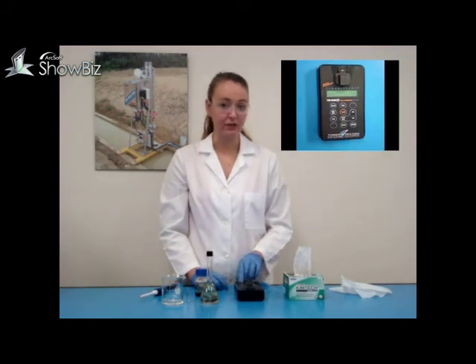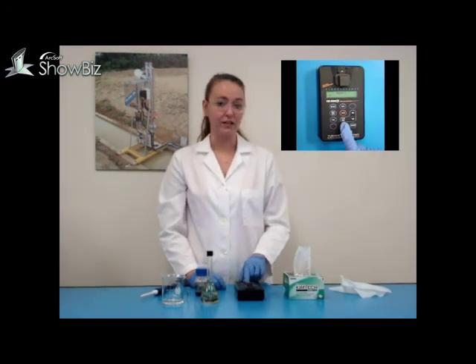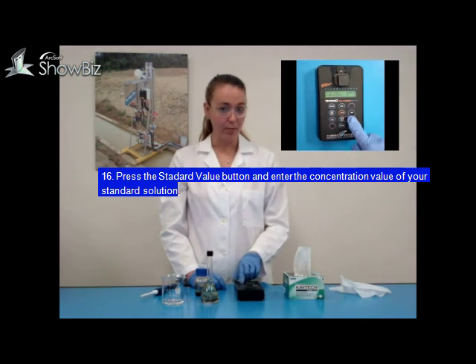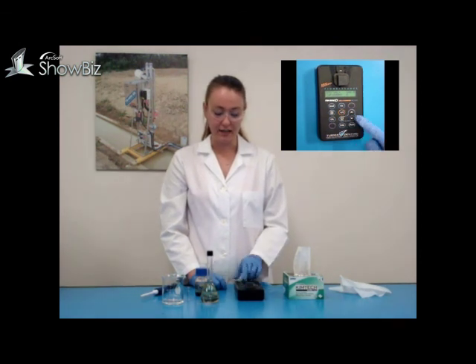Your TD-500D will now tell you that it has been calibrated. You have one last step until calibration is complete — you must tell the instrument the concentration of your calibration standard. Press the standard value on the instrument and using the up and down arrows, change the value displayed to match the concentration of your standard solution. In this case, our solution is 100, so we will set the value to display 100 and then press enter. Your TD-500D has now been calibrated for the solvent extraction method.